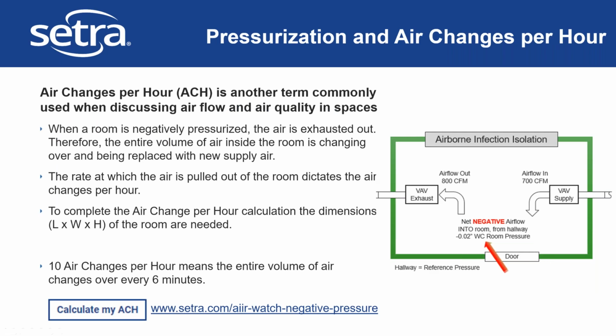I want to talk about air changes per hour. This is another very commonly used term when thinking about airflow and air quality in hospitals and in areas where you are looking to effectively isolate people and effectively protect people from contaminants in the air. When a room is negatively pressurized, the air gets exhausted out. So the entire volume of air inside of that space is actually changing over and being replaced with new supply air. In hospitals where this is designed into their buildings, this is all achieved through the HVAC system.